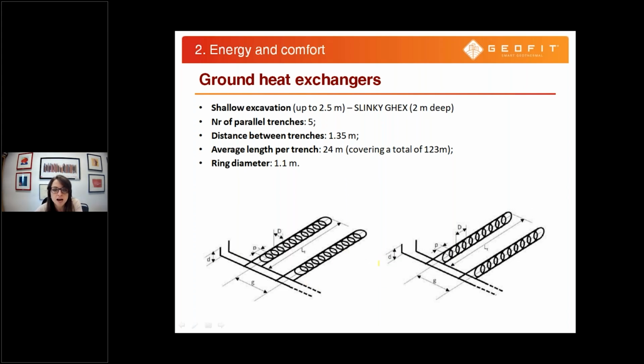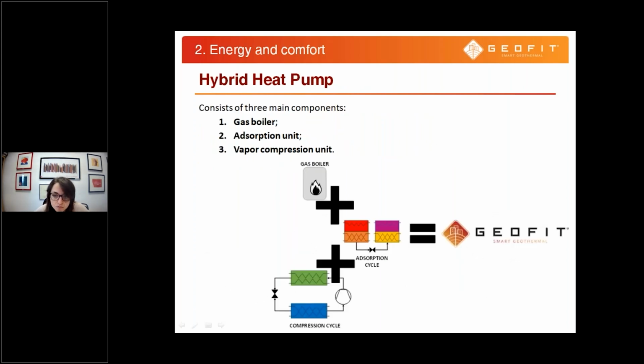The design team went through the calculations, and we decided to use 5 trenches of this slinky GHEX with a main distance of 1.35 meters between each of them, and a ring diameter of 1.1 meters.